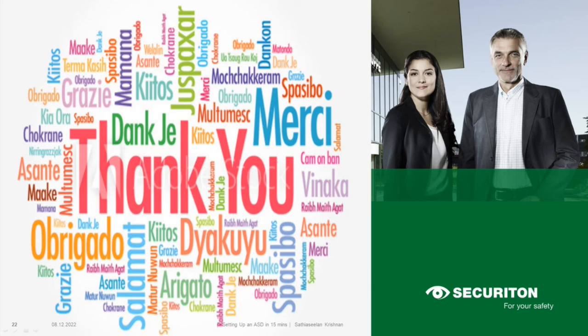Seelan, we have got a few questions, and the first question is, in what format is the information saved on the SD card and how to view it? Perfect. So inside the SD card, as I mentioned, 640,000 events are stored in Excel format. So when you retrieve this information, put it into your card reader in a PC, and you are able to get the Excel file, and you can also see smoke concentration values as well.